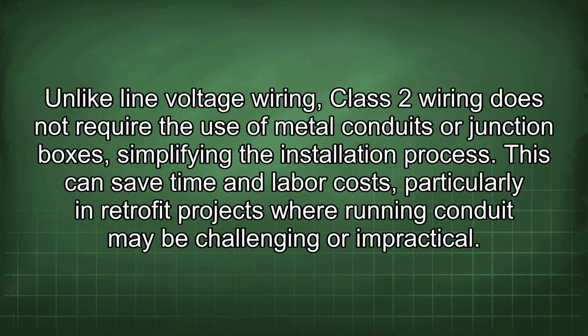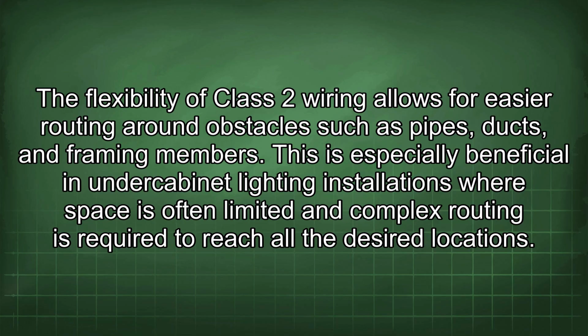Unlike line voltage wiring, Class 2 wiring does not require the use of metal conduits or junction boxes, simplifying the installation process. This can save time and labor costs, particularly in retrofit projects where running conduit may be challenging or impractical. The flexibility of Class 2 wiring allows for easier routing around obstacles such as pipes, ducts, and framing members. This is especially beneficial in under-cabinet lighting installations where space is often limited and complex routing is required to reach all the desired locations.